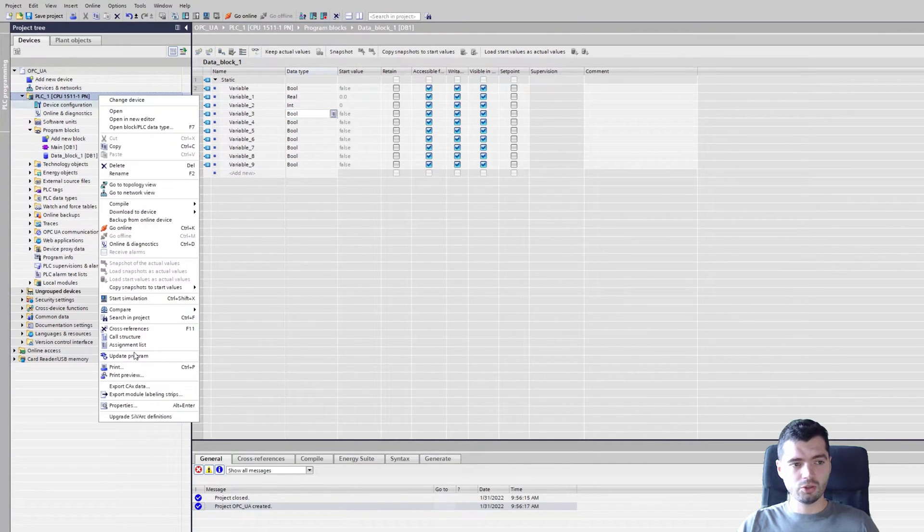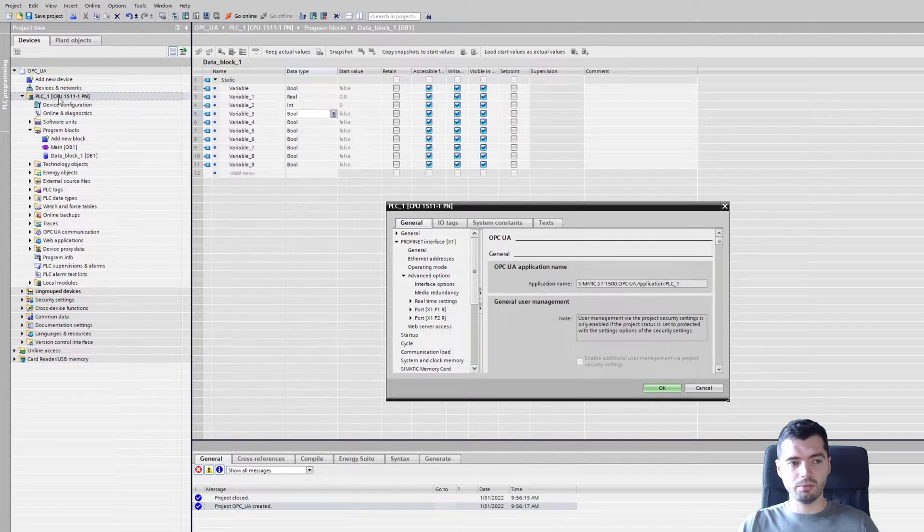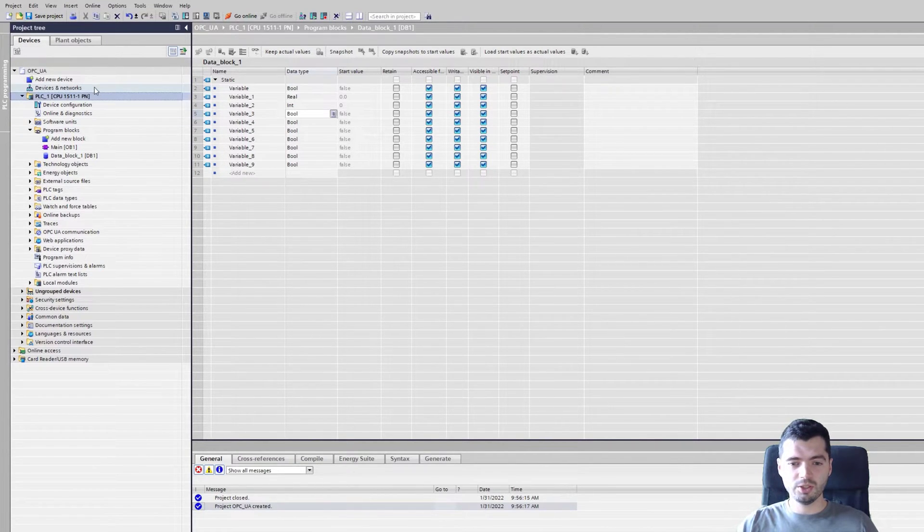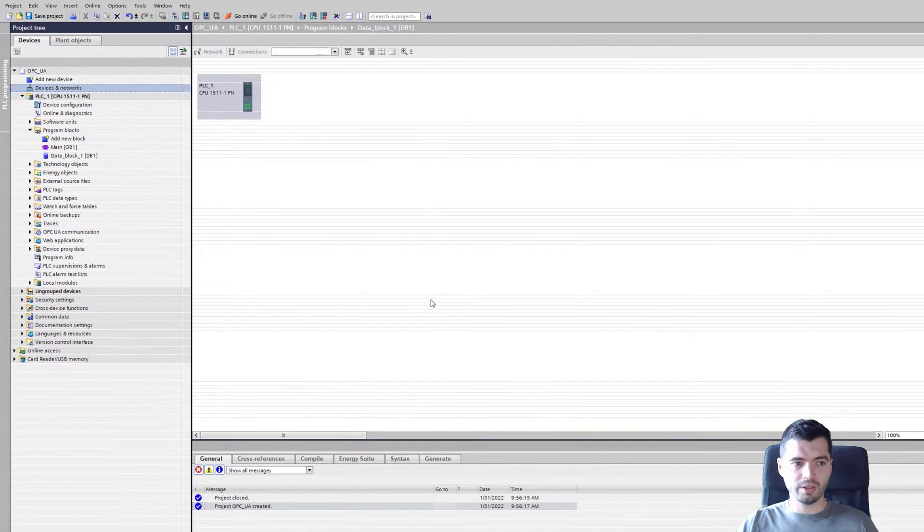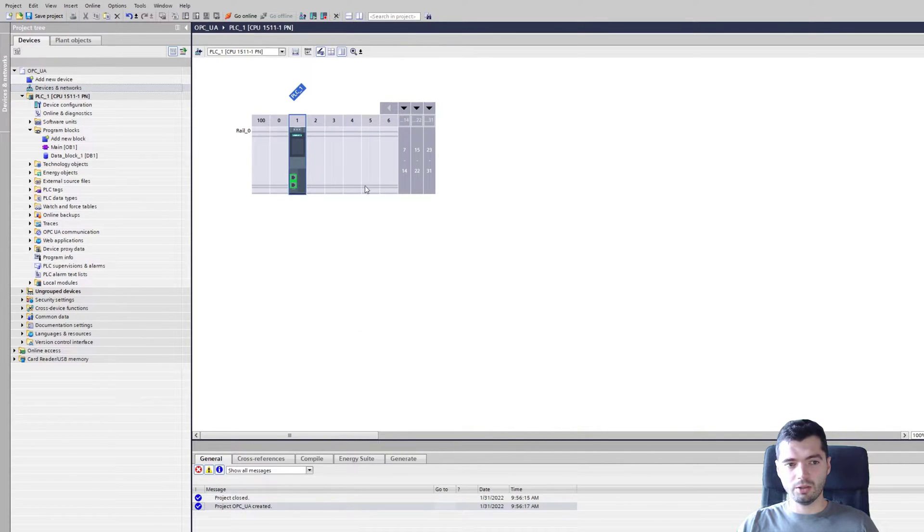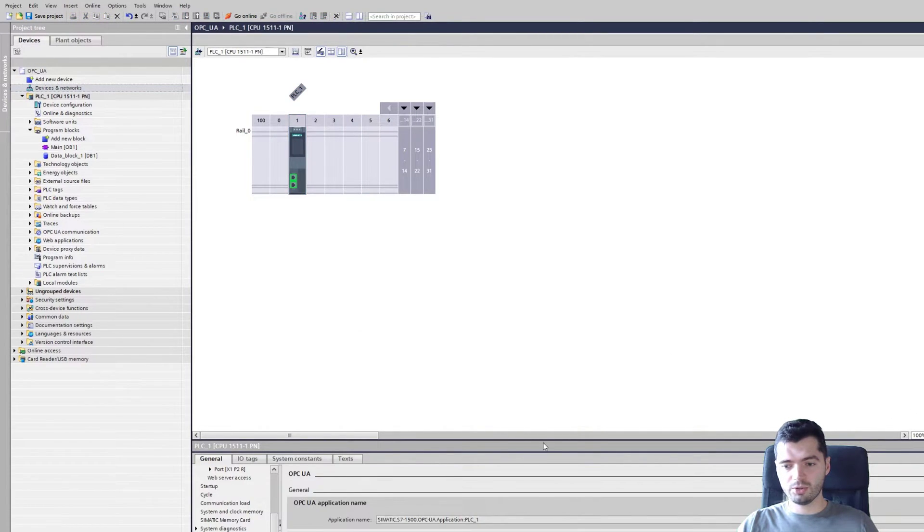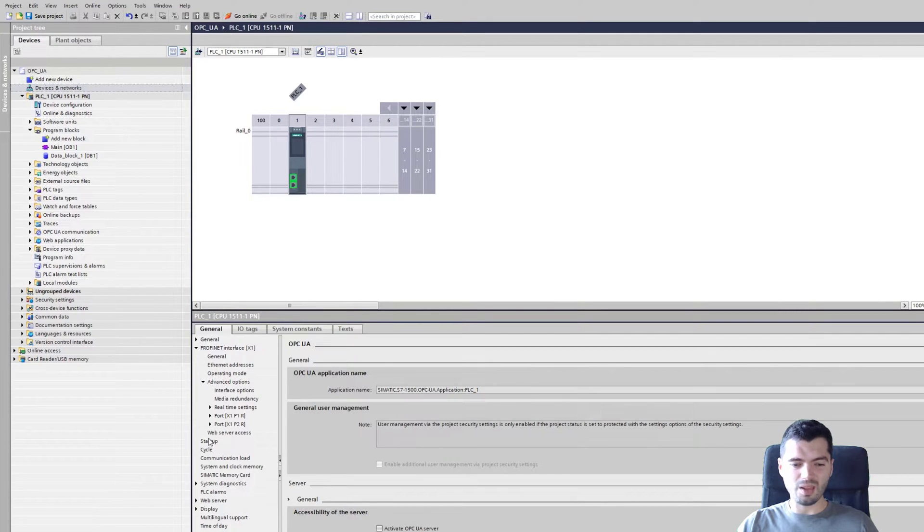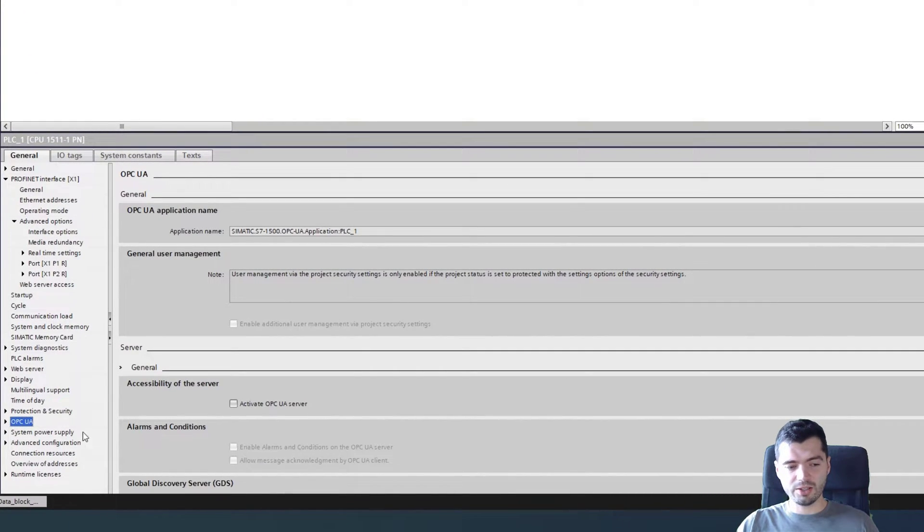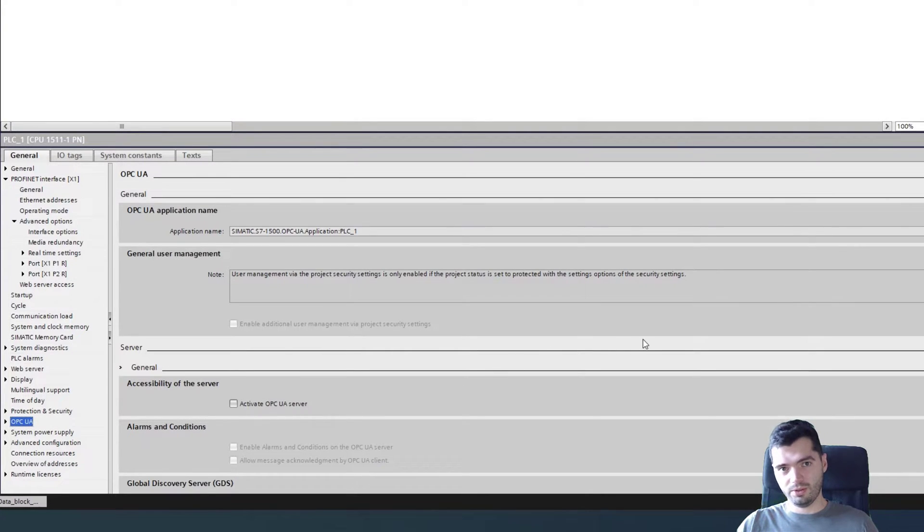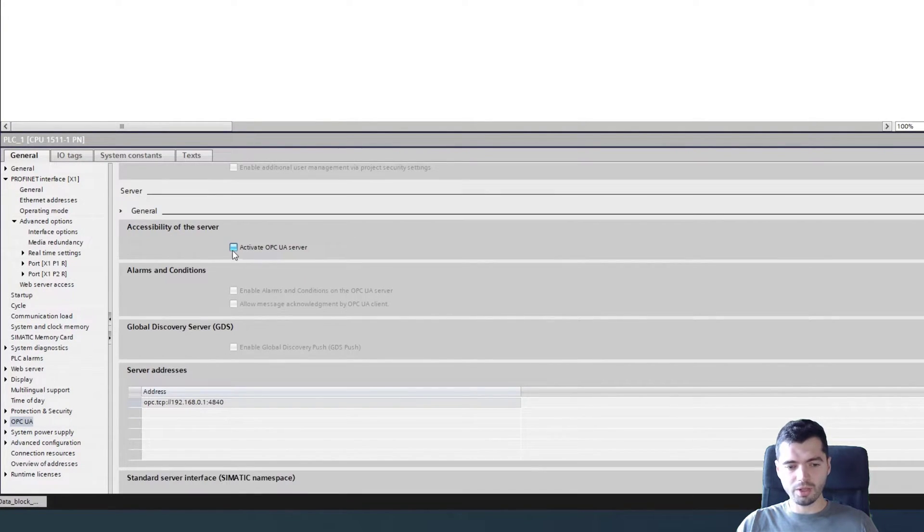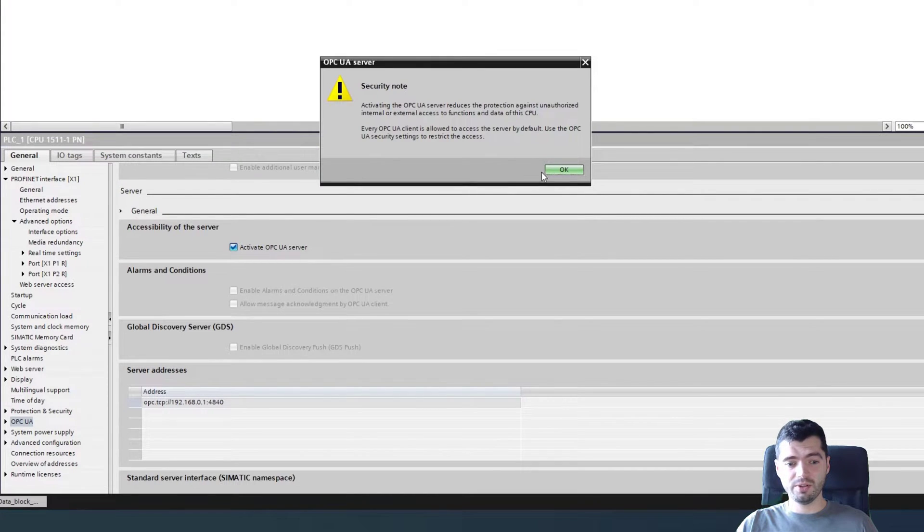If you go to the properties, right click on the CPU properties, or another place, devices and networks, go to your PLC, select the PLC, go properties. It's exactly the same place. You have obviously a list of all different properties. One of them is OPC UA. If you scroll down, you have a tick box. So you just tick activate OPC UA server.